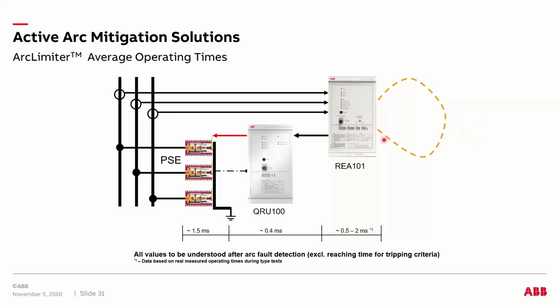And once you have a fault detected, an arc fault detected, the REA 101 has a reaction time of less than 2 milliseconds and sends a signal to the QRU, which we call the quick release unit, or the electronics controlling the UFS element, right? So it takes another 0.4 milliseconds to send the trip signal to these primary switching elements, right? Then the UFS elements take about 1.5 milliseconds to connect the bus bars to the ground, right?